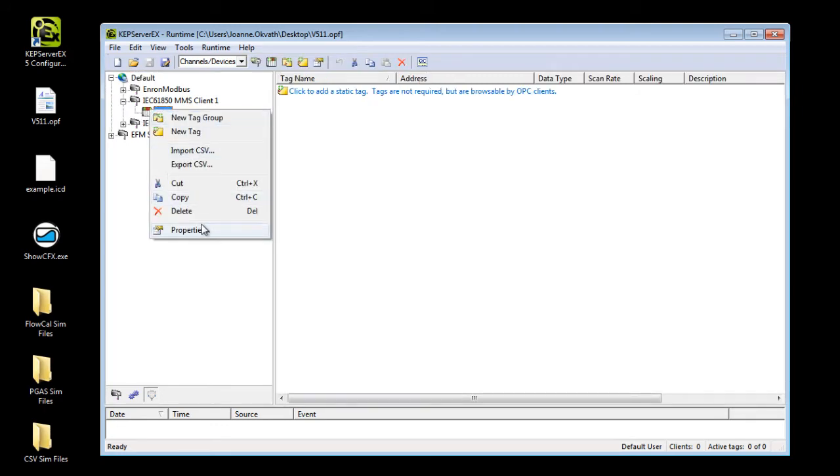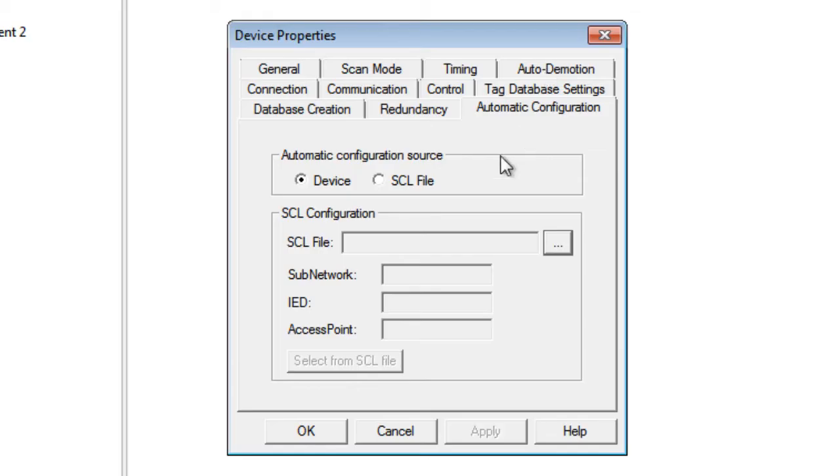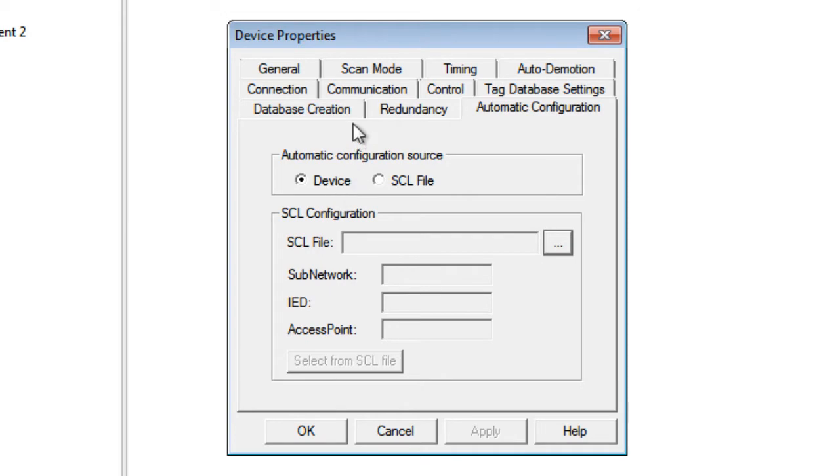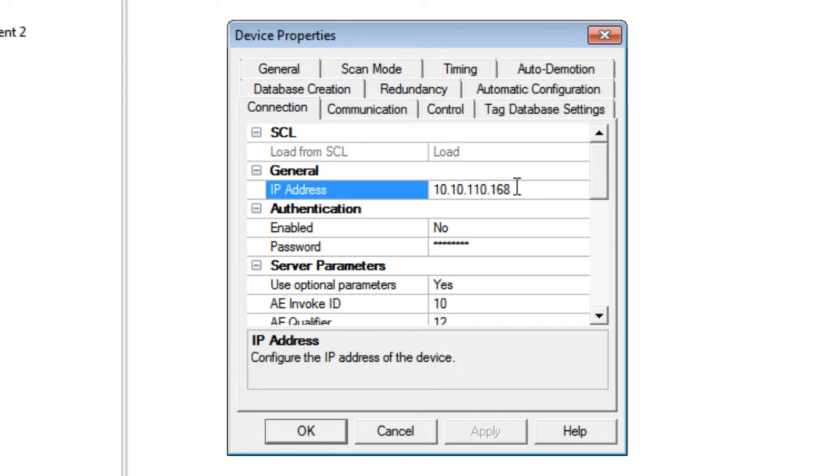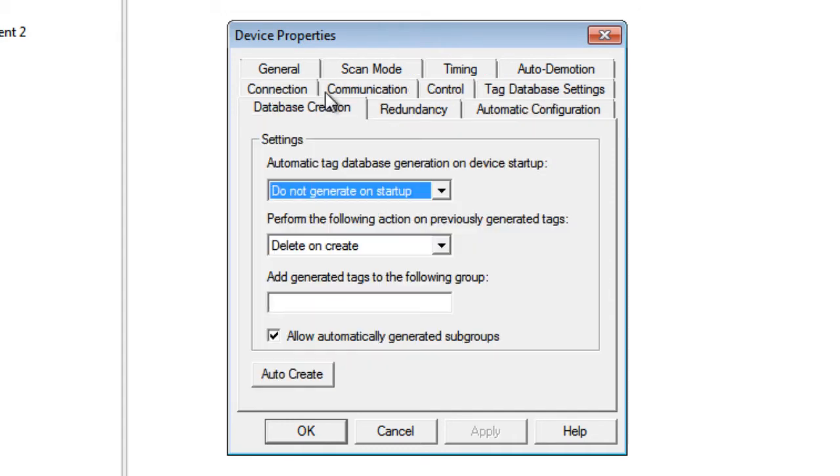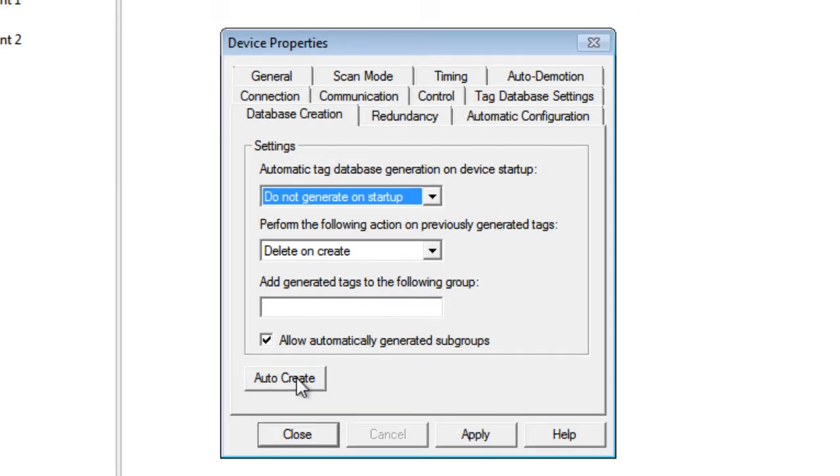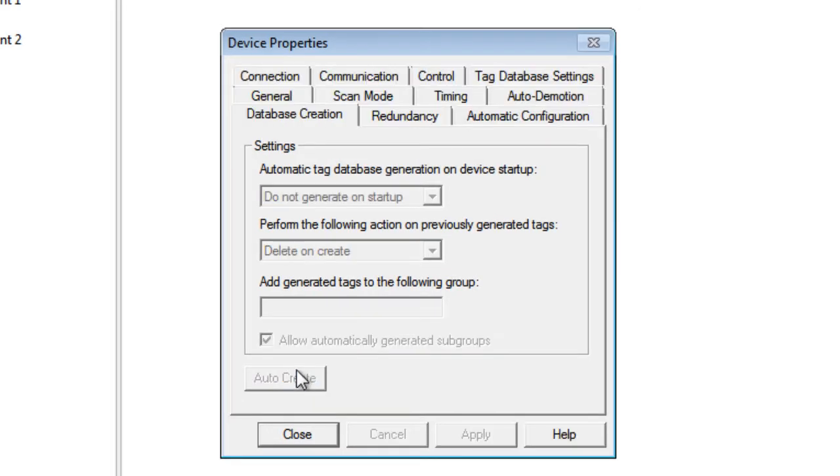When setting up a new device in the device properties window, users have the option to pull register information from a connected device or the SCL file and populate the server with this data. Going to the connection tab, we can see that you can load the IP address from the SCL file or enter it manually, and that is all you need to automatically generate tags. Finally, browse through the database creation tab and click auto-create to automatically generate device tags.